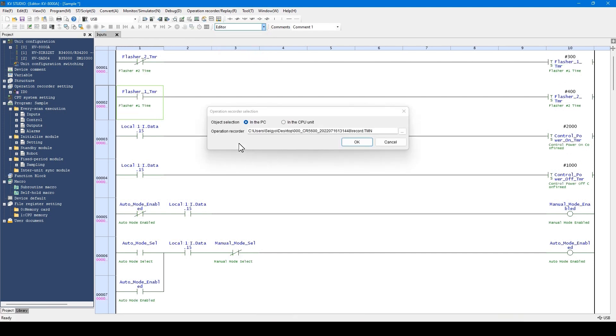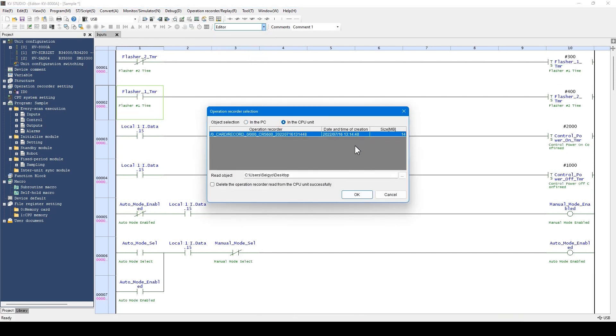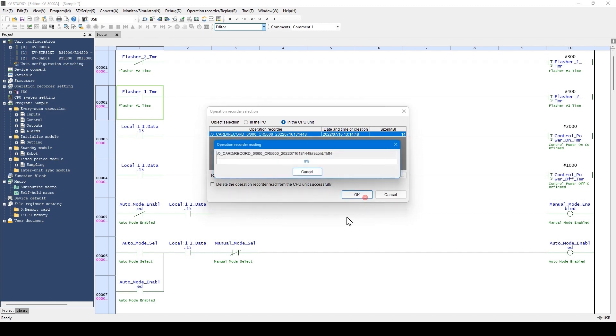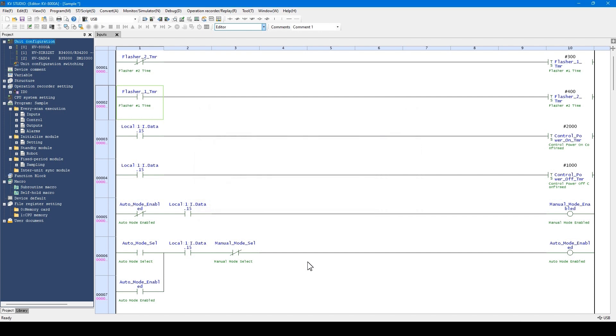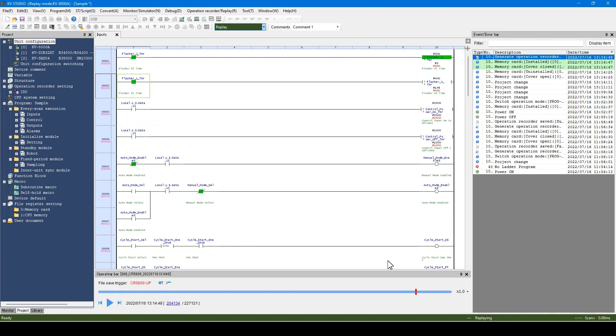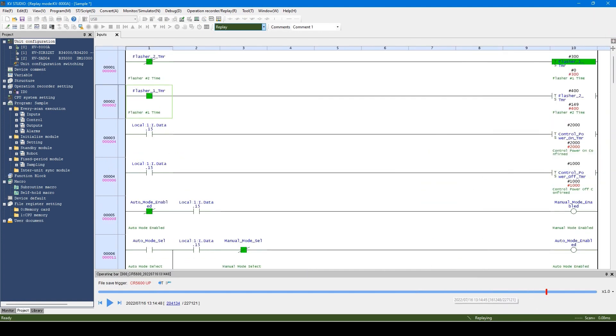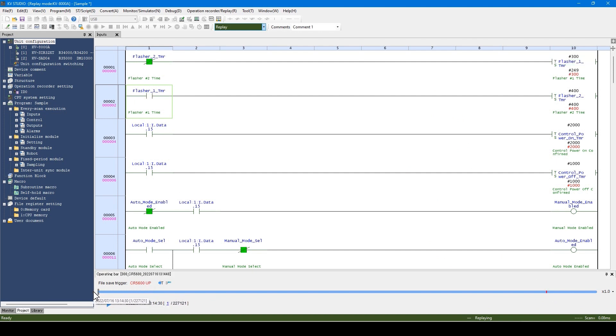In replay mode, you can load and play the operation record data from the CPU unit. Such operation record data are saved by using the operation recorder function. When loading completes, replay mode starts. Operate the replay bar and then click the replay button. Now you can check on your PC the performance history of the PLC program.